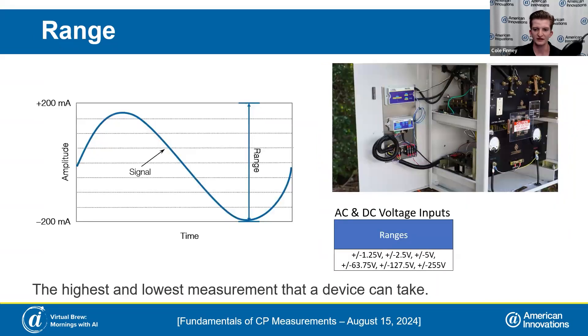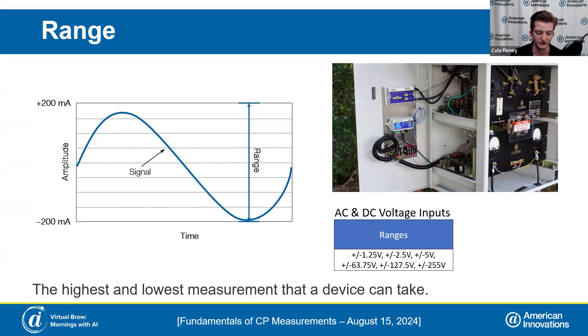The first one we're going to talk about is range. Range is the highest and lowest measurement that any measurement device can capture. On the left I have a simple waveform with a signal of plus or minus 200 milliamps as the highest and lowest measurement — that would be your range. Looking at the specs for the RM510, our remote monitor for a rectifier, you'll see that range can vary for DC and AC current. On a DVM, you'll probably encounter a plus or minus 250 volts or greater, and on a rectifier monitor, all the way up to almost 300 volts.